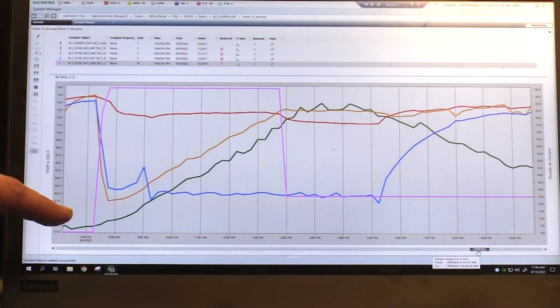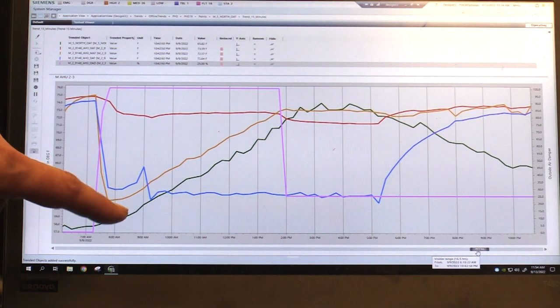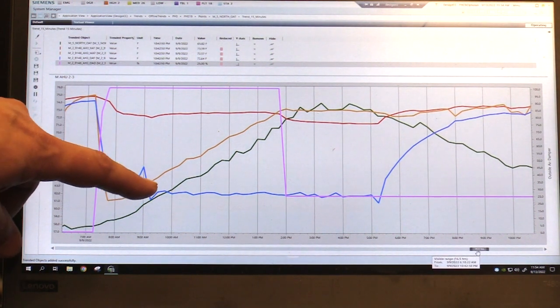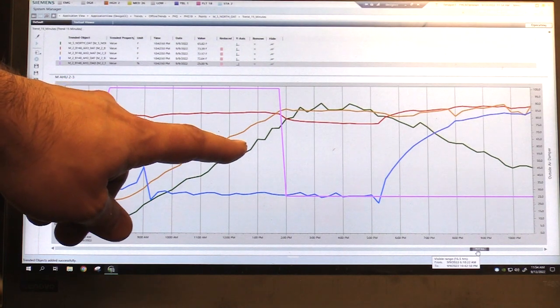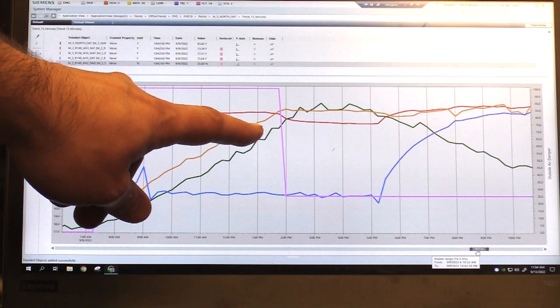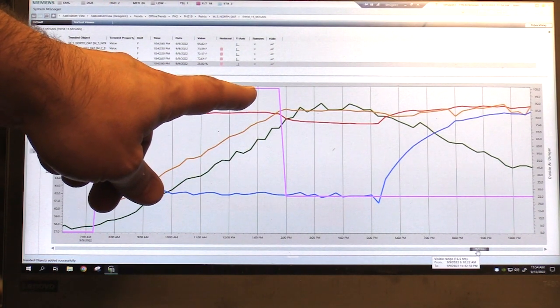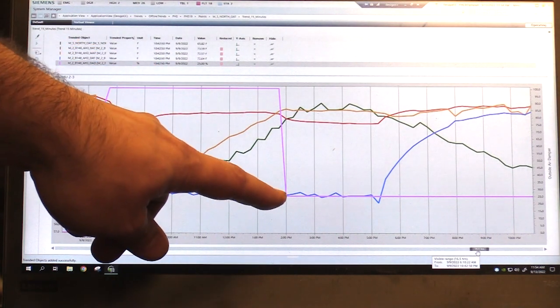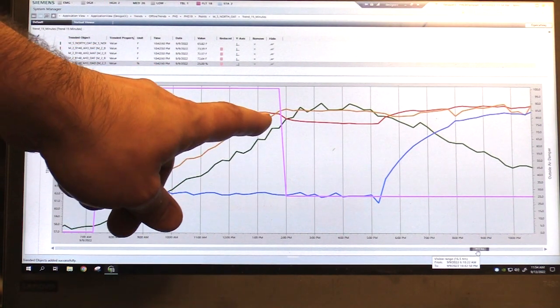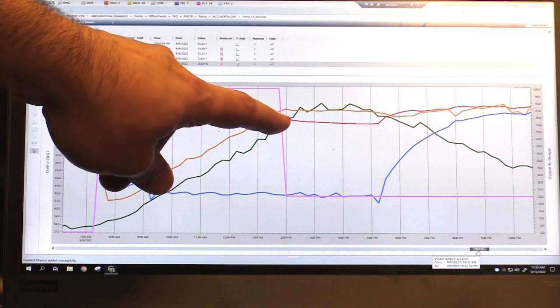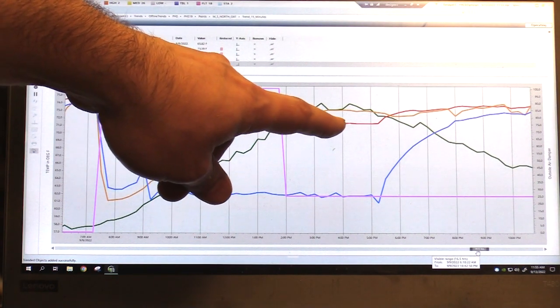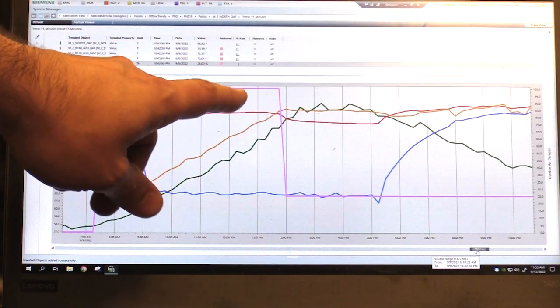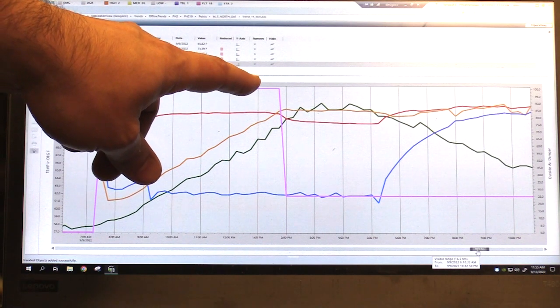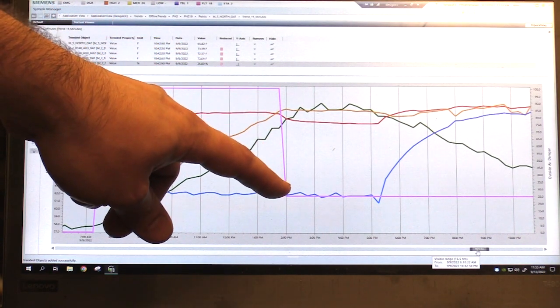You'll see that when the air handler starts, the mixed air temperature is going to be tracking our outside air temperature. At a certain temperature outside, around 72 degrees, you'll see that the outside air damper goes to its minimum position at 25%. And our mixed air temperature starts tracking now with our return air temperature. Because we're in cooling season, the outside air damper is going to either go from 100% to its minimum position, depending upon the outside air temperature.